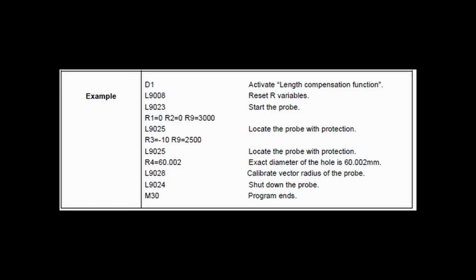The example shown here has an additional element that the eccentricity calibration omitted. L9025, which starts the probe with protection. If I understand the example program correctly, it looks like the probe is centered 10 millimeters above the ring gauge as shown on line 4. R1 equals 0, R2 equals 0 represents X0 and Y0, and R9 is extra moving distance. Then the probe moves down 10 millimeters as shown on line 6 with R3 equals -10.